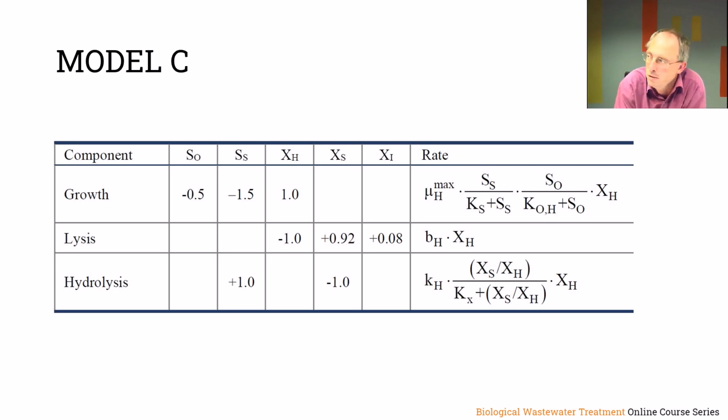So you have again two types of inert matter. Inert COD, which comes in with the wastewater, and inert COD, which is produced in the decay process. The rest we can all leave the same, we assume, and the rate equations we also don't need to change, because we only added an extra compound, so different stoichiometry, not different rates. And it's also logical that we did not need to change the rates, because effectively the form of the OUR curve was described quite well.